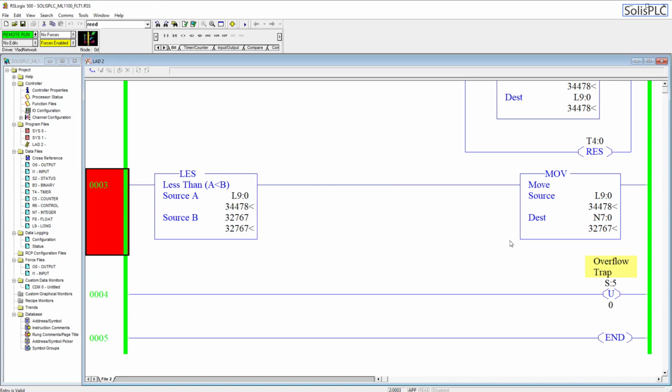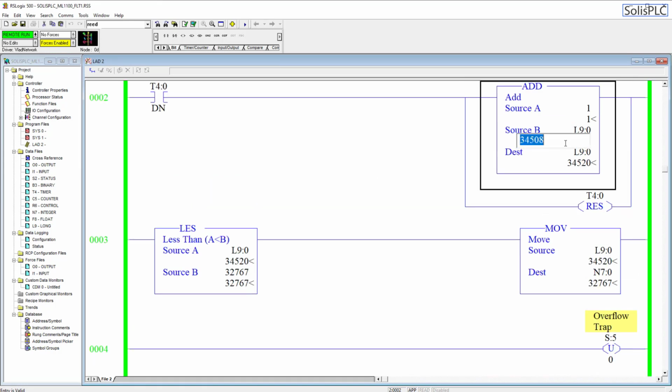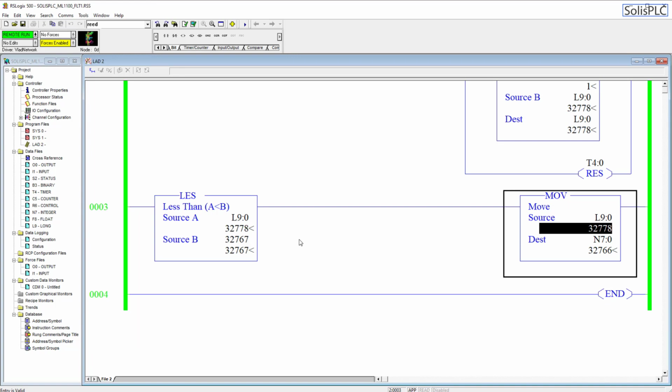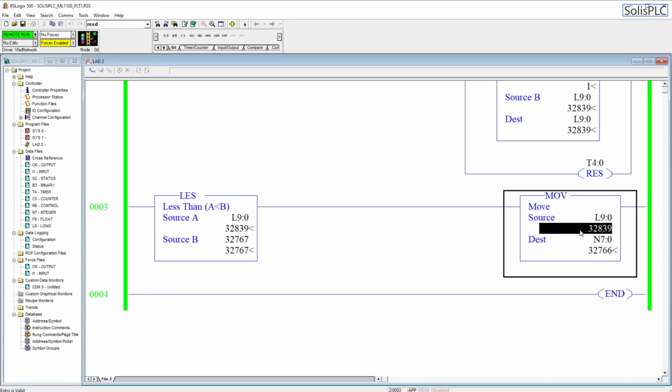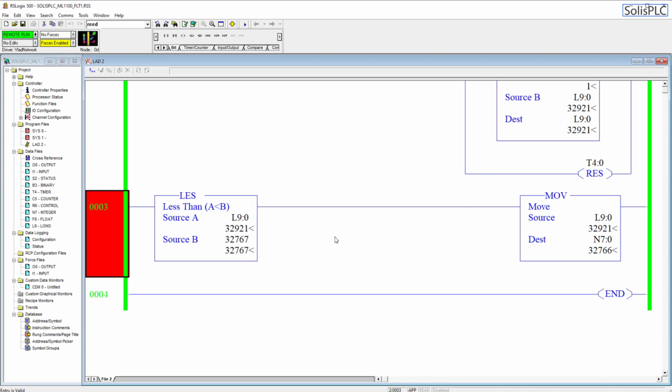And we have the overflow trap already. What we could do is, let's say, set this to 32,000, and we can actually delete this. It's another way to prevent that specific error, but ultimately it's not solving our problem necessarily. Like I said, you can implement some kind of a mask, or some different way to pass your information wherever it's going, but ultimately we figured out how to keep the PLC running. It's back to normal condition and it's able to execute the instruction as you would expect.